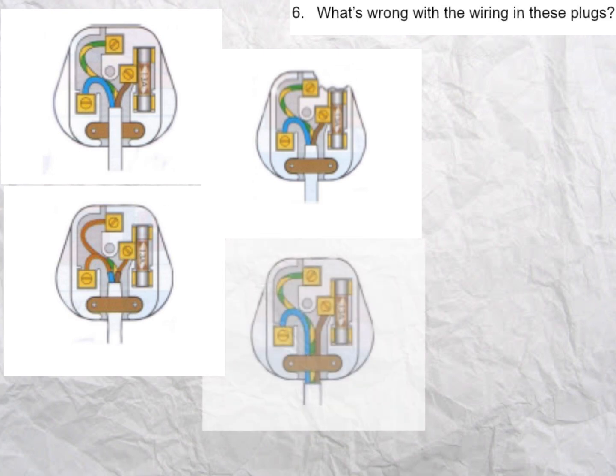The fourth one looks okay at first glance, but it's a really common and serious error. The cord grip is gripping individual wires and not the outer plastic cord. In use, the wires will get easily pulled out of the plug, possibly causing a short circuit. We need to shorten the exposed wire a little and grip the outer cord in the cord grip instead.